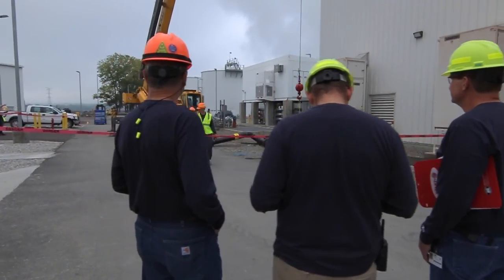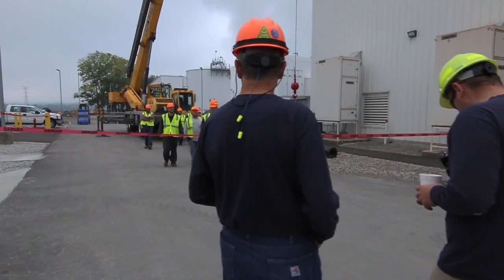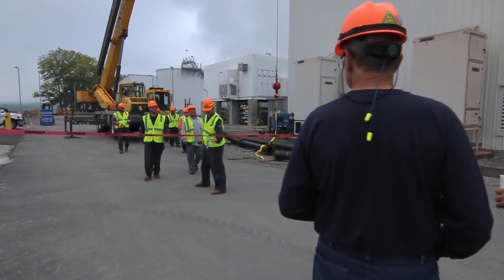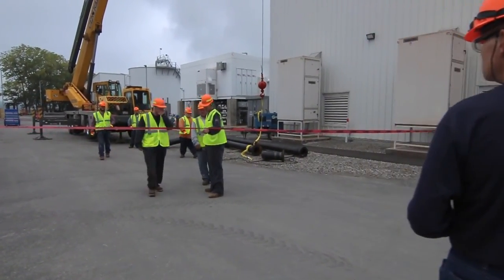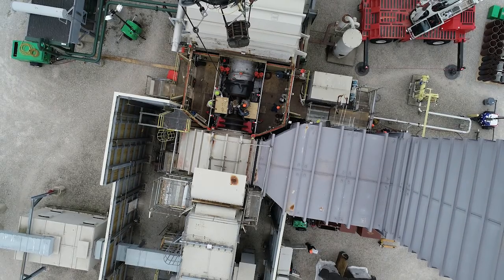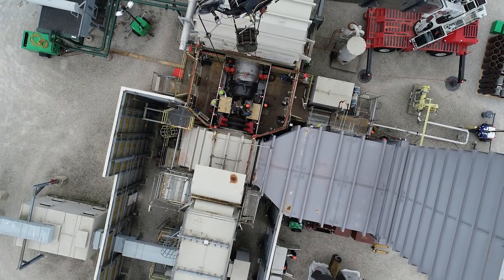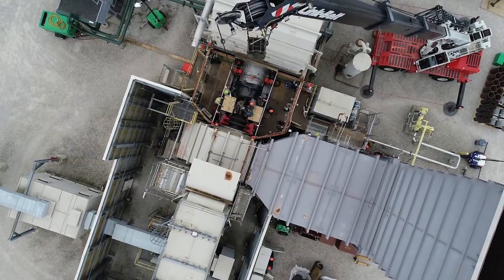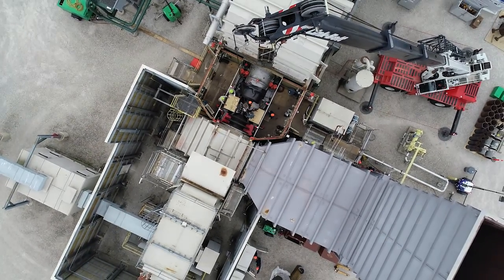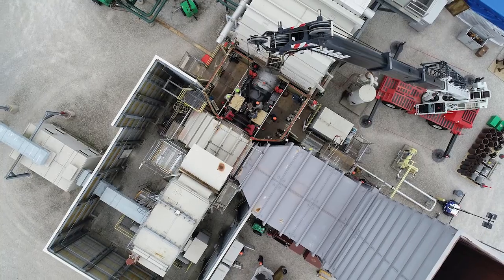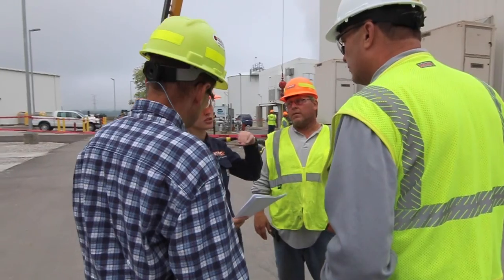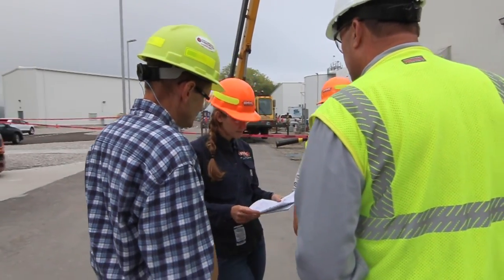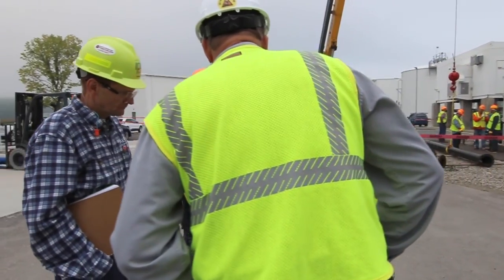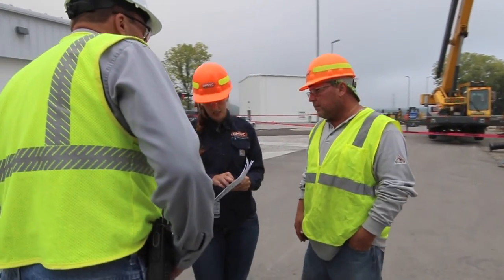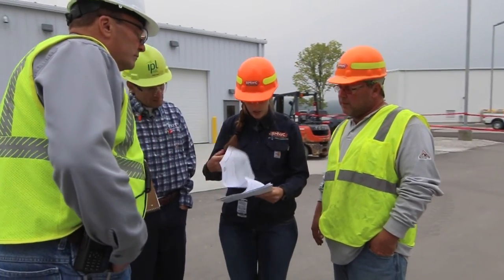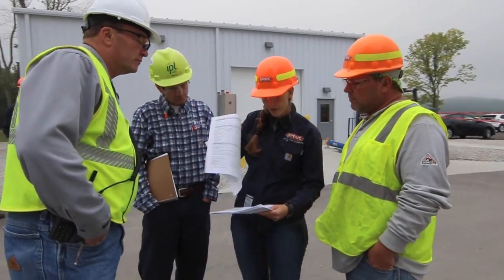Areas where lifting is taking place shall be appropriately marked with caution tape to effectively prevent people from walking into the area. The use of a spotter is required. If you are operating a mobile crane or any boom-equipped heavy equipment requiring a boom to be extended near electrical lines or equipment, a qualified employee shall first identify the voltage present, verify the electrical status of the lines or equipment, and provide you with the applicable safe work clearances you shall maintain.